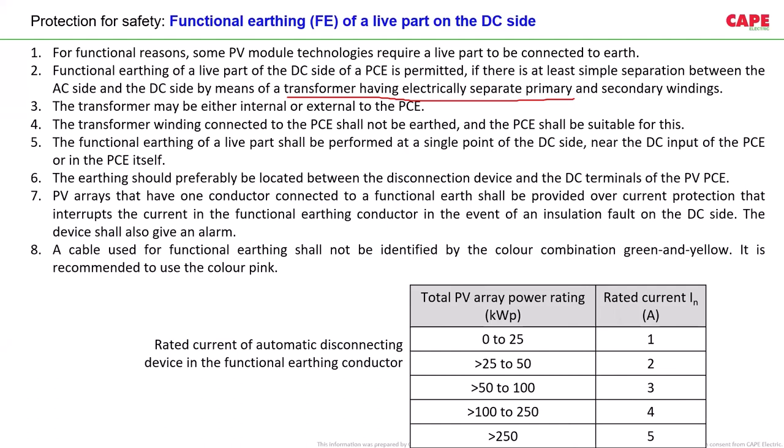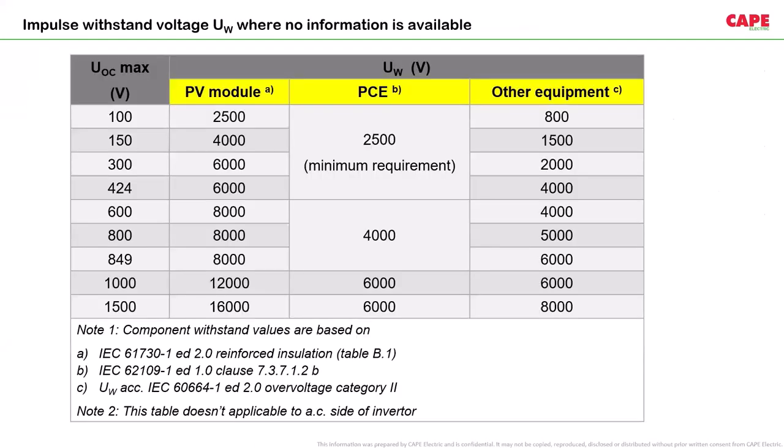As I said, through the functional earthing, depending upon the capacity of the installed PV array, you are supposed to measure the current and you are supposed to disconnect. Similarly, impulse voltage, safety against over voltage, each part of the electrical installation of the PV must withstand certain impulse voltage. Of course, in the PV module, these impulse voltages are ensured by the PV module manufacturer, depending upon its voltage.